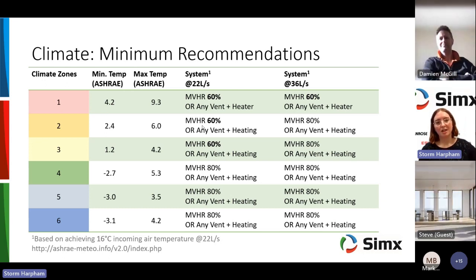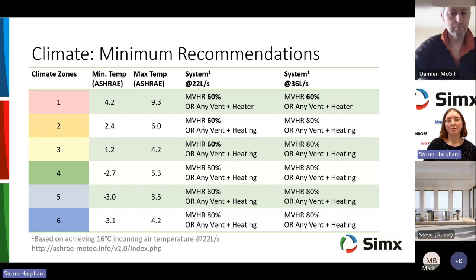We found that you could actually use anywhere in the country an MVHR solution, but when you went from climate zone 3 to climate zone 4, you needed to make sure the efficiency of your core was higher. So that might be looking at cross-flow versus counterflow cores, where oh my goodness, too many C's. Cross-flow versus counterflow cores, where in the counterflow, there's a higher efficiency due to the air staying in contact for longer. If you're looking at a bigger house, though, that 60% dropped down to only working in climate zone 1, and you needed to go to 80% all the way through. You'll also see that in here we've said that you can get that temperature up to 16 degrees by using any ventilation solution with a heater.